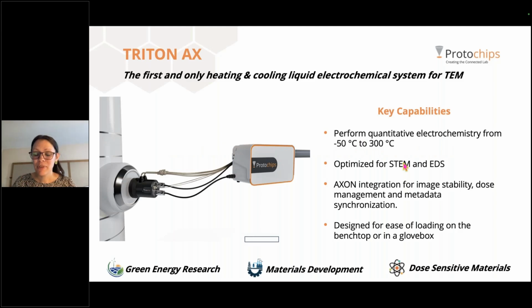So again, reviewing the key capabilities for the system here, you're performing quantitative electrochemistry from -50 degrees C up to 300 degrees C. And again, you don't have to do electrochemistry. You can just apply temperature in liquid without the electrochemical stimuli too, which broadens the flexibility of the system. It has been optimized for STEM and EDS measurements in liquid. You don't have to remove the liquid in order to obtain really nice STEM images to help control the dose or to obtain EDS maps. You can if you want to, of course, but you don't have to. You can keep that true in situ environment while you do those measurements.